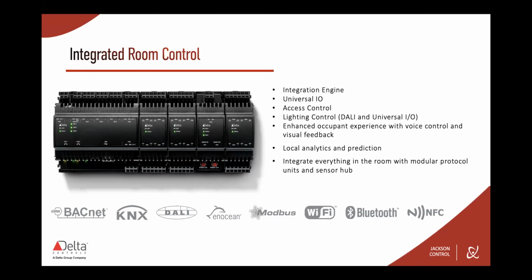It has dual port Ethernet, so you don't have to worry about home running a whole bunch of Cat5. You can essentially do a daisy chain of Cat5 through it. There's a number of different RS-485 ports, so it can pick up Modbus, we have a module for DALI, LON. We've been working with KNX, but basically any of the major building automation type network protocols, we can do integration to.